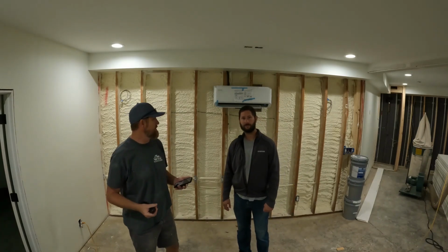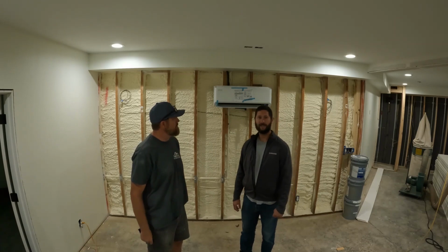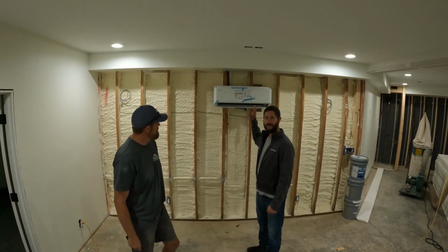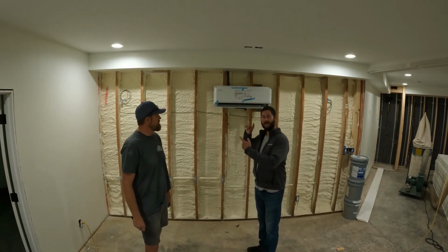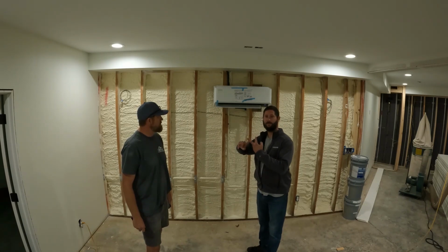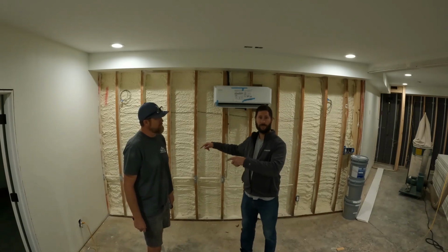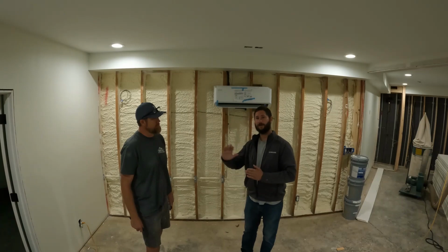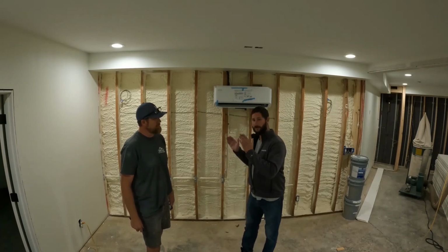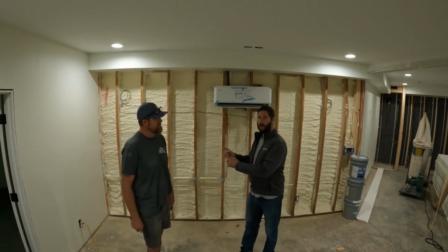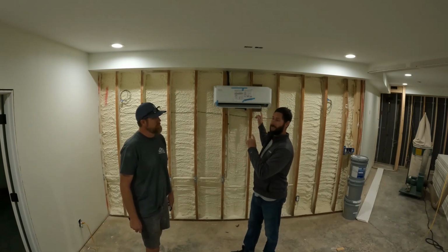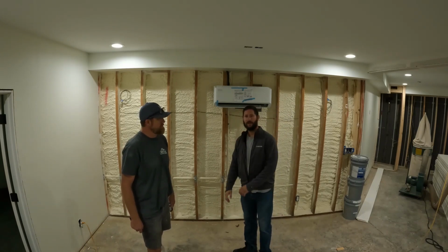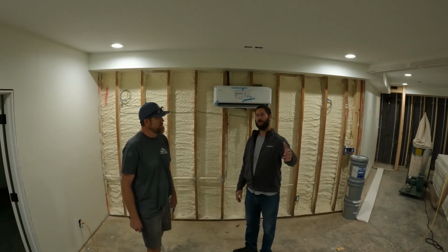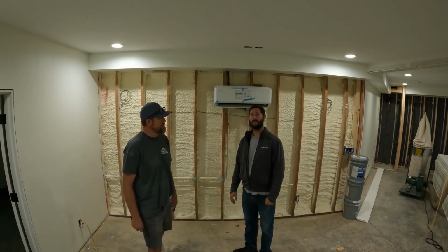Okay. Do the heads need power? Yes, the heads need power. Each indoor unit has a cable. It has a power cable and a communication cable that come directly from the outdoor unit. The outdoor unit has to have a breaker and a wire go to it, and then from the outdoor unit you have a wire and a power cable and a communication cable that come to each indoor unit. And I think it's 14 gauge for the power wire, and I think that it's 16 gauge for the communication wire.